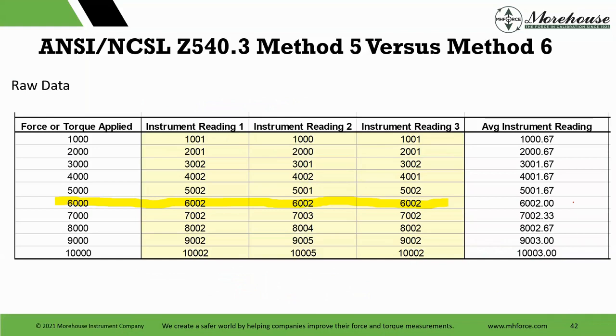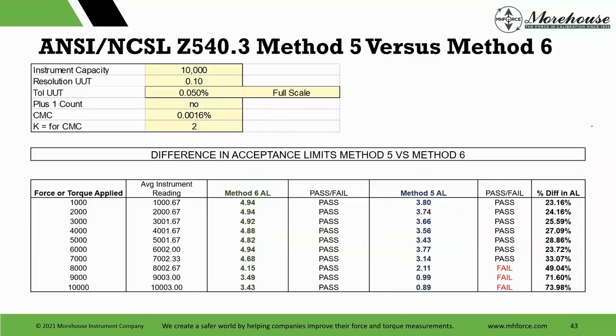Here's some raw data that we have, just looking at different points, average instrument reading. So if we did a load cell, someone said, hey, I have a 10,000 pound device. Let's do 3 runs from 1,000 to 10,000, and we found this. That's just average data to do some comparisons with. Then the customer says, I need my tolerance to be 0.05% of full scale. So we run both methods. You can see method 5, where we're subtracting that calibration process uncertainty, versus method 6. And one of them is going to say pass the instrument, and the other one's going to fail.